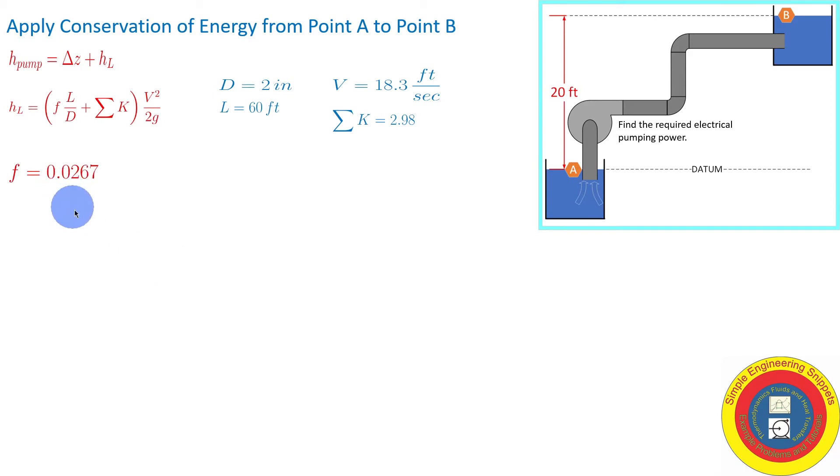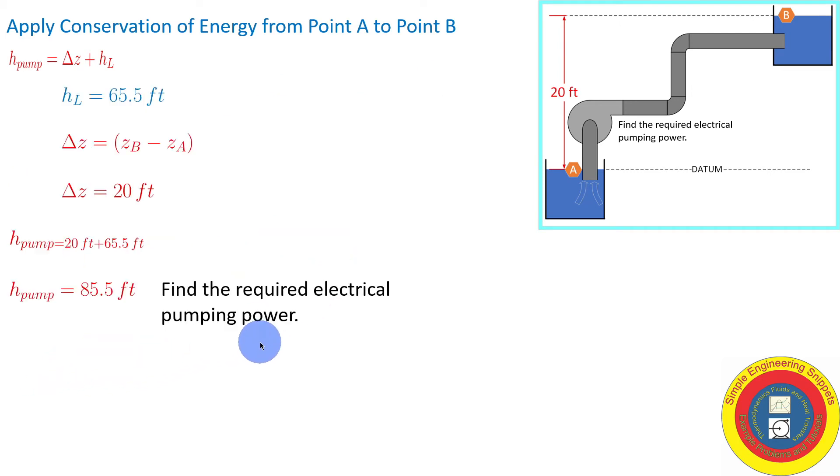So we have the friction factor. Now we can calculate the head loss. It comes out to be 65.5 feet. Now that we know the head loss, we already knew the change in elevation. It's a simple matter to calculate the pump head. It's 85.5 feet.